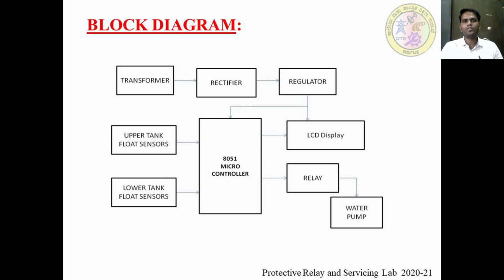The upper tank float sensor is connected to our overhead tank, which gives the condition of the water, whether low, medium or high, and the lower tank float sensors are connected to my sump, giving the level of water in the sump, whether low, medium or high. So according to the condition of the water level in both tanks, the motor is turned on and off.